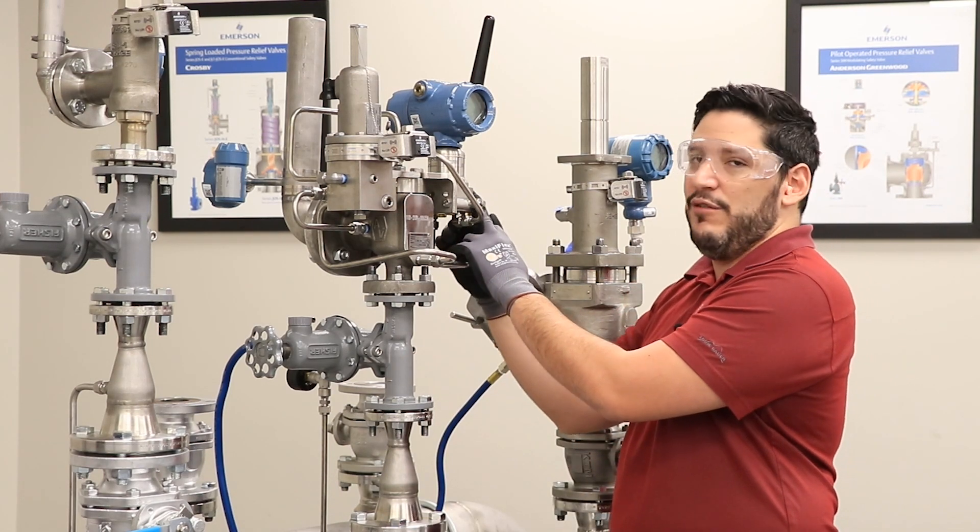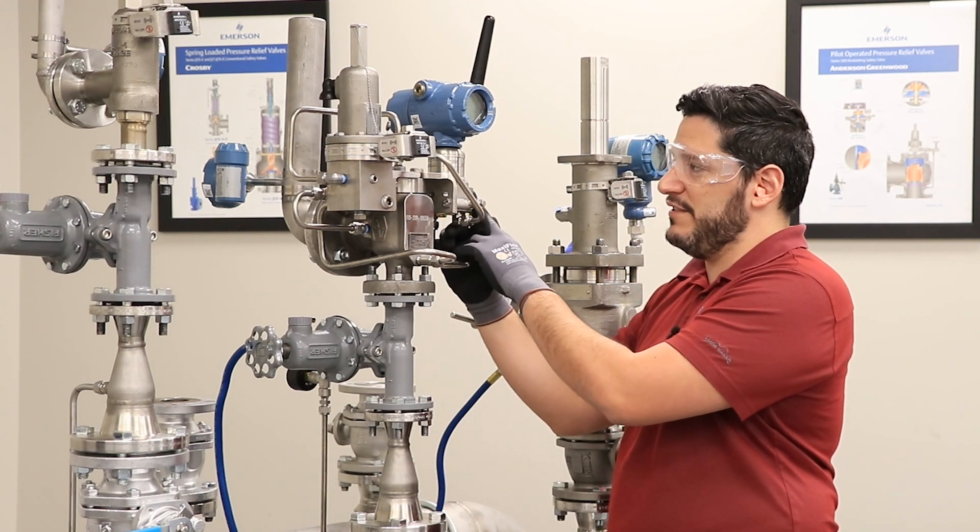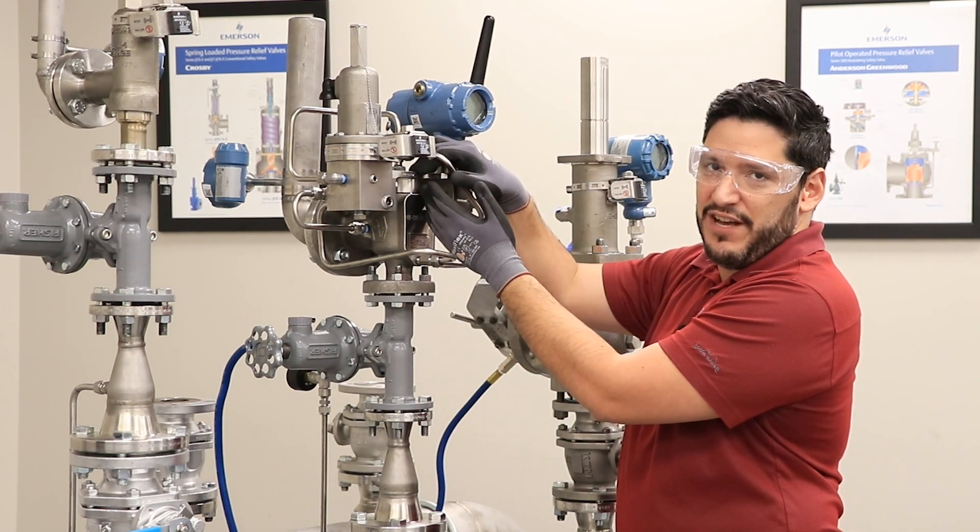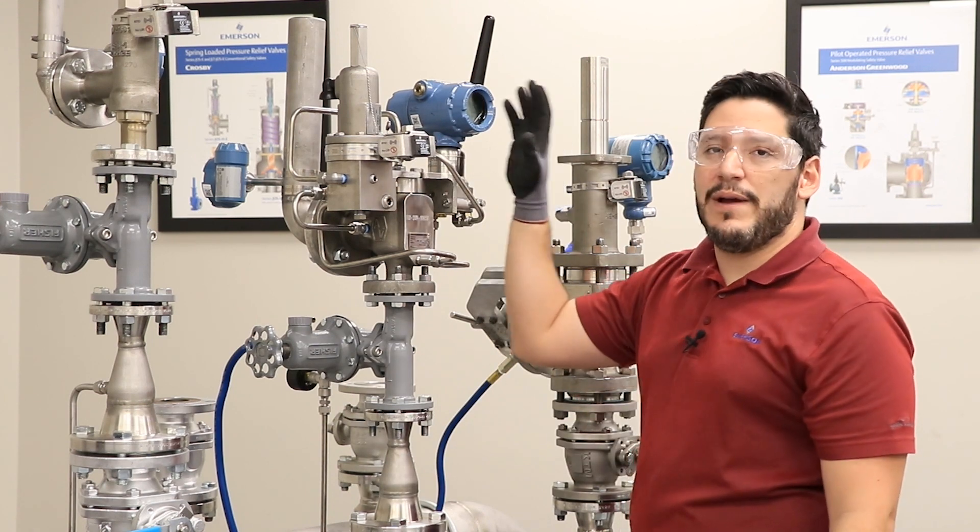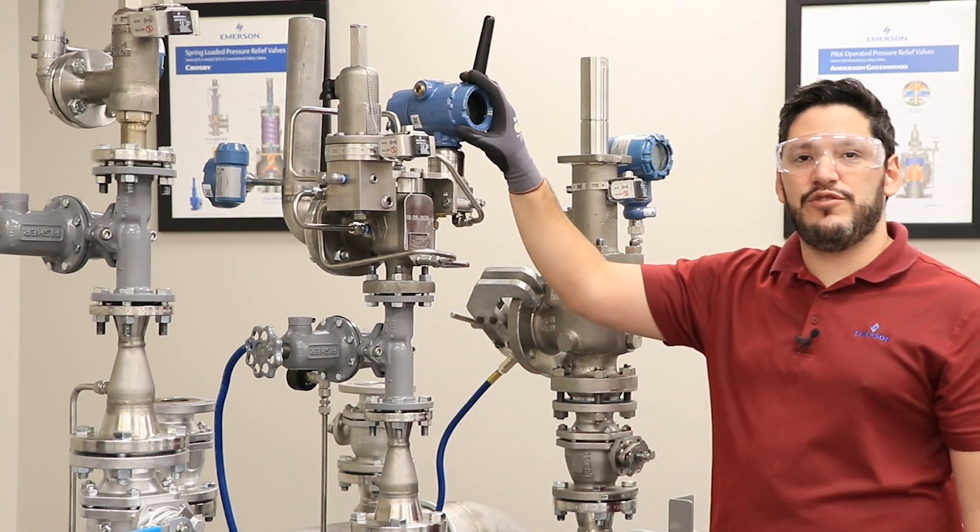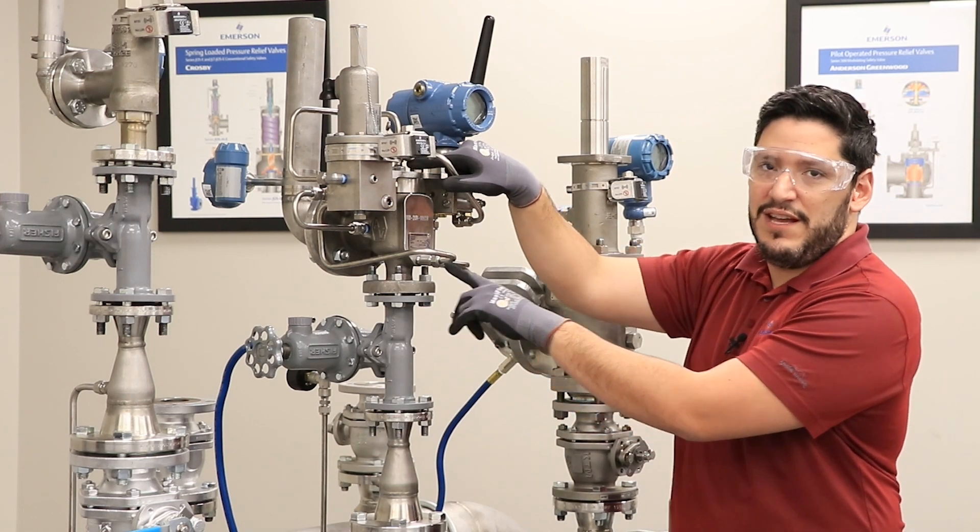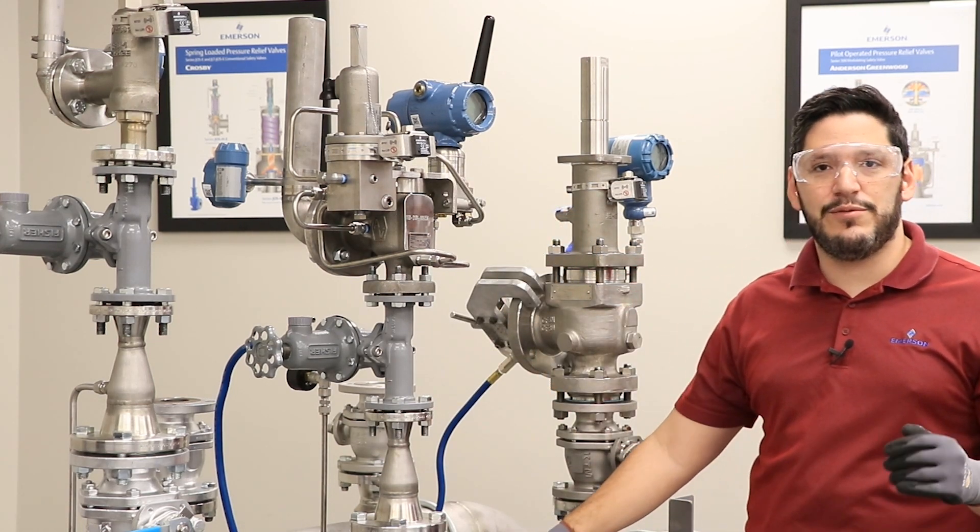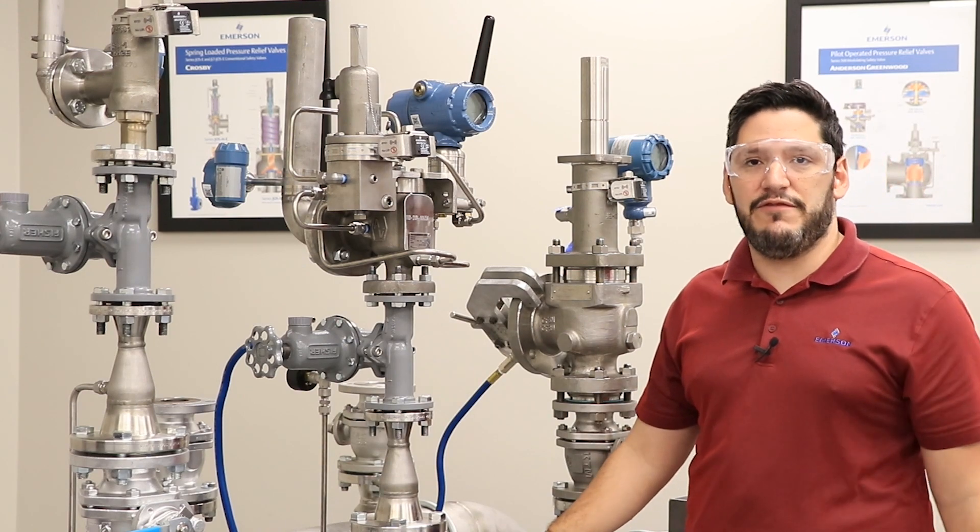And we take the low side of the differential pressure transmitter into the dome on top of the main valve. There is a direct correlation between the differential pressure between these two points and the valve lift percent. There is also a direct correlation between valve lift percent and flow.